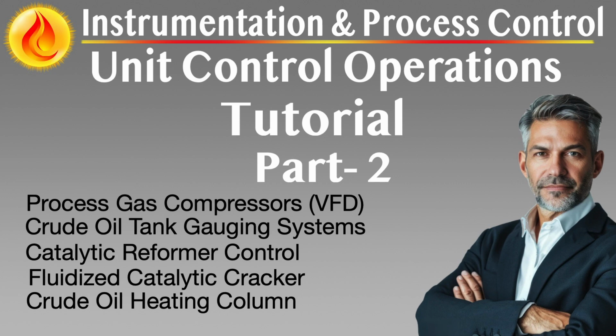In modern facilities, tank gauging systems are integrated with temperature and pressure sensors to calculate volume compensation and convert gross volumes to standard volumes using API 2540 ASTM D1250 volume correction factors. Multi-point temperature sensors are placed along the tank height to capture thermal stratification, while pressure sensors help determine vapor space conditions. This integrated approach enables precise computation of net standard volume (NSV), total observed volume (TOV), and water cut, critical for both operational reconciliation and commercial invoicing.